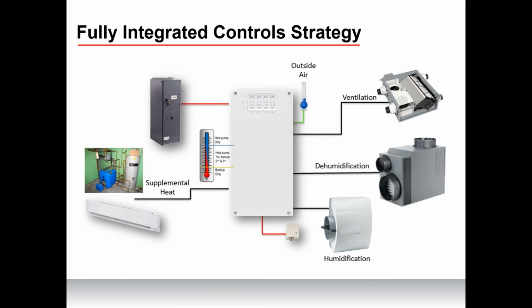What I primarily like to use this application for is the left-hand side of this slide. This Kumo Station specifically is a great way to integrate supplemental heat. Just look at that box in the middle and think of it as a relay box, right? It's going to tell that system when to turn on that backup heat and when to turn that backup heat off. You're going to optimize it based off of outdoor air temperature.